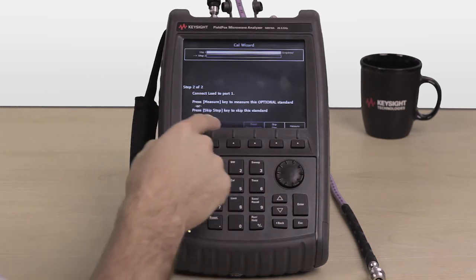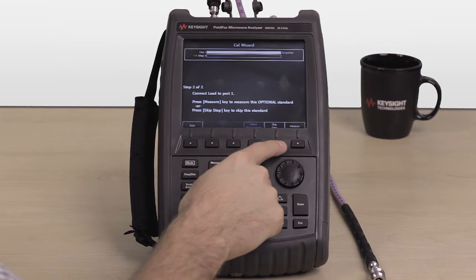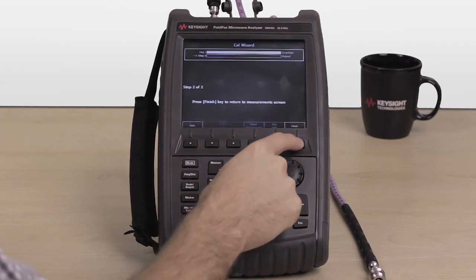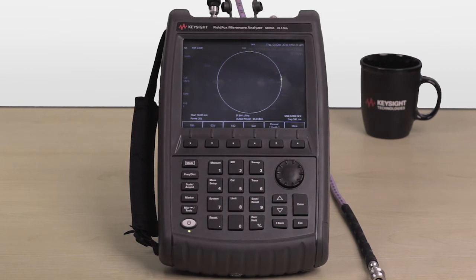That's once this calibration is complete. We're going to skip this step because we don't want to connect the mechanical standard right now. Press Finish. And what do you know? We have our impedance set at around infinite ohms.